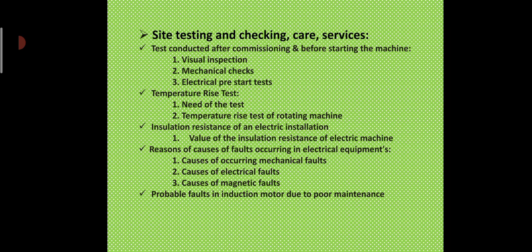There is wastage of energy when the machine is loaded fully and the temperature rise is measured. So it becomes costly, and the use of this method is limited to small capacity machines. Moreover, for large capacity machines, it is difficult to get a load of large capacity.